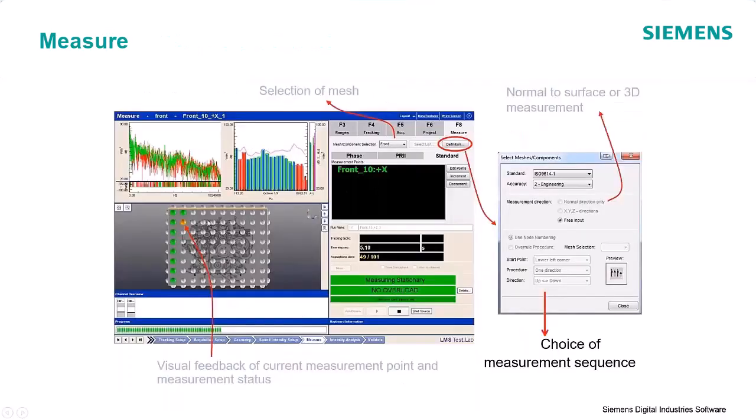What you do in the intensity measurement is go through point by point wherever you want to measure. As you are measuring the data, it gives you a status indicator of where you are measuring. It shows in green which points have been completed and what the next point is. It also shows you the live measured intensity, and where the intensity is with respect to the upper limit and lower limit. Here you can see the measured intensities are under the upper limit. There is a lower limit as well, based on the PRII. It's a good visual indicator.